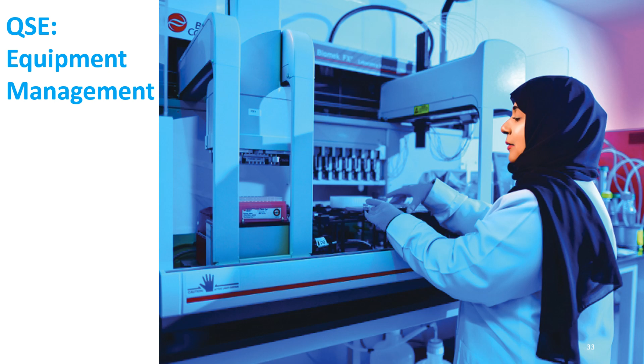The following should be considered before purchasing the device. Quality essentials for establishing an automated process include device qualification. As I mentioned previously, we need to put in the specification, installation qualification, operation qualification, and performance qualification. These will be discussed in detail by our colleague Monika in the next part of the presentation. All equipment used should be documented. Our equipment maintenance is tracked through a master list of equipment.